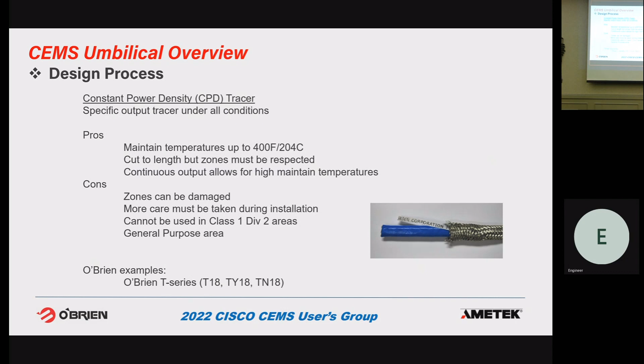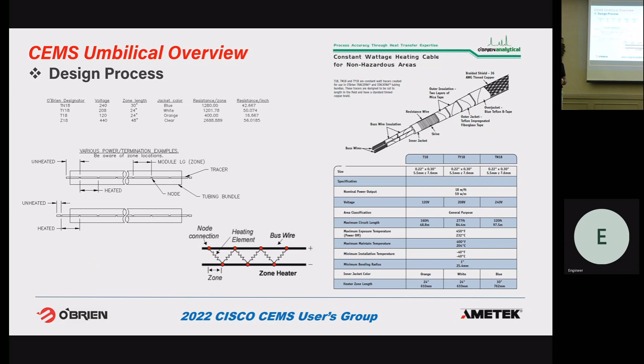In the lower of the two, we've got a chart. I don't know if I have it in here. Here it is. Whatever that number is, let's say that's 200 ohm, the lower of the two. Let's say you were using this TY18 tracer. You would then divide that by 50.074, because the resistance of that is 50.074 per inch. That will tell you how many inches away you are from that next node. We've tried having it marked, and since this tracer has an external braid, that braid moves around and it's too difficult to try to accurately get that.